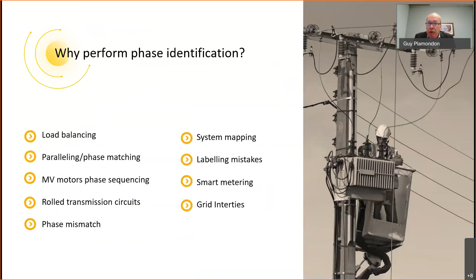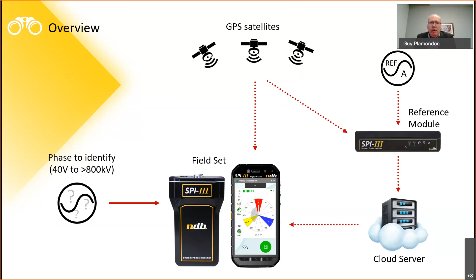Here's an overview of the way it works. We install a reference module on a known A phase on the customer's network, and use GPS satellite timestamps, sending them to a cloud application. The field unit itself has a built-in GPS antenna to take these timestamps as well, and when a measurement is performed, we use the cellular network to compare the reading in the field with the reference. Then it gives us the phase angle shift.